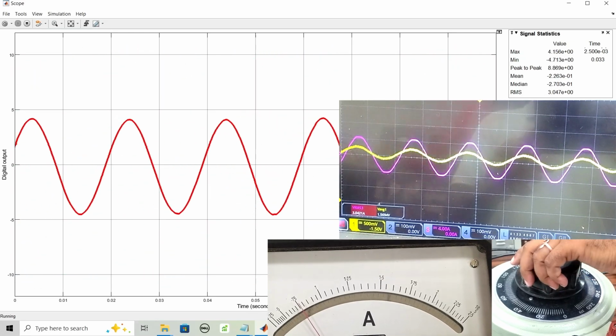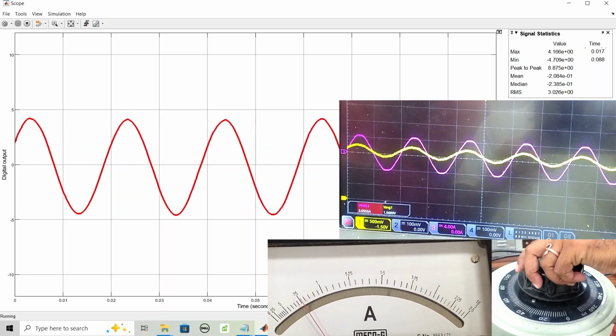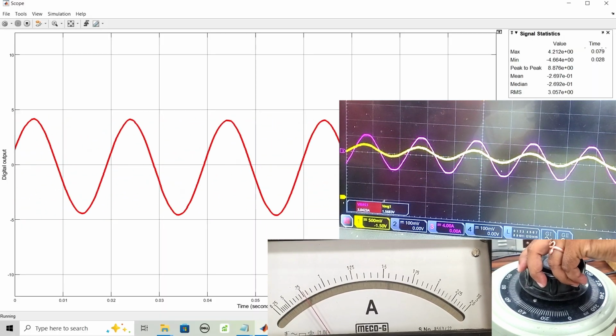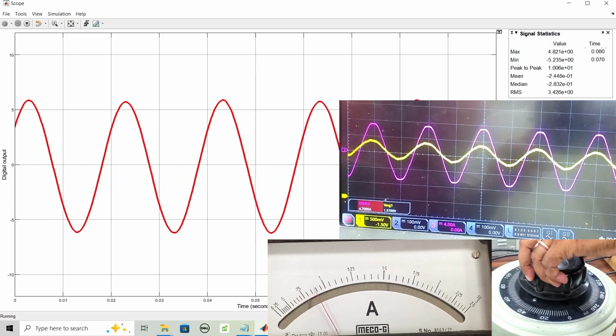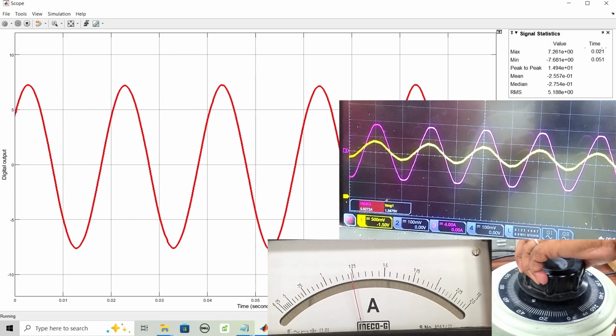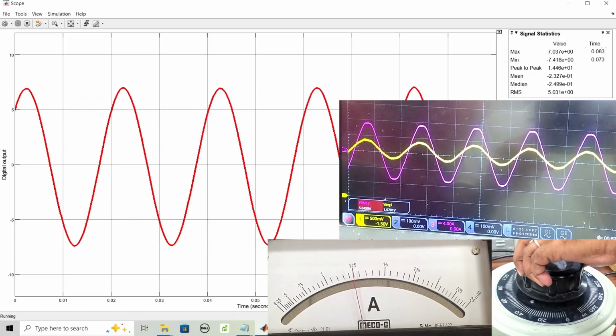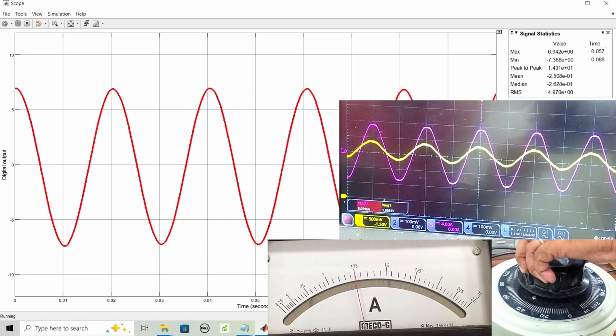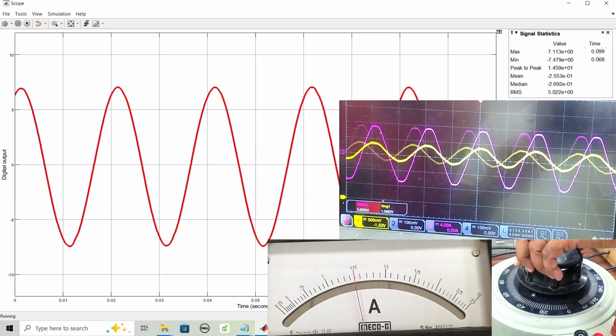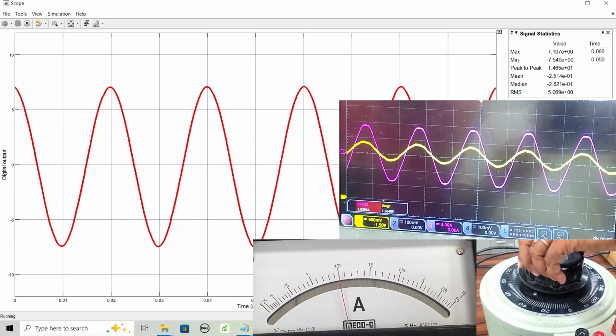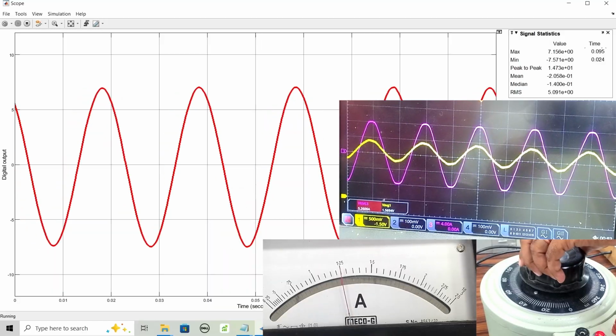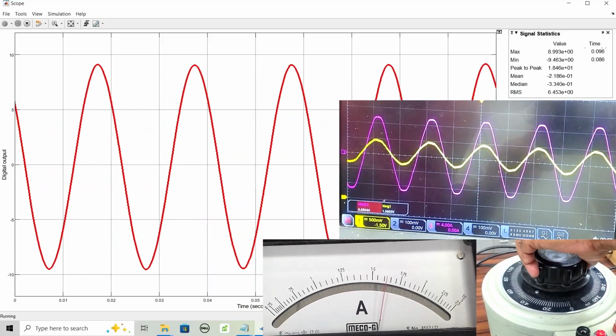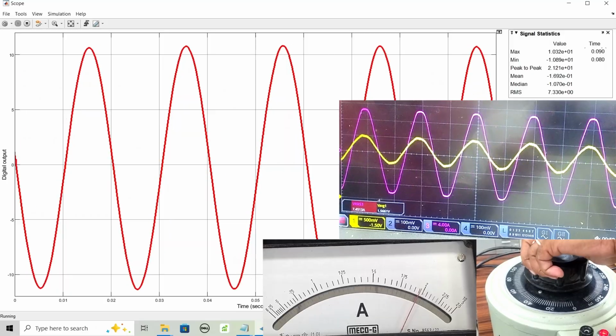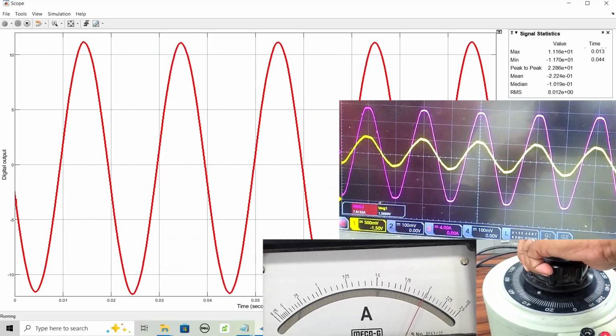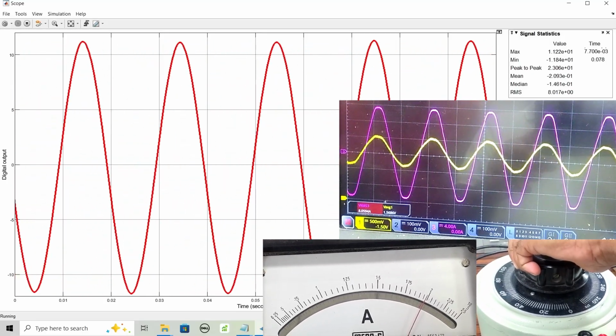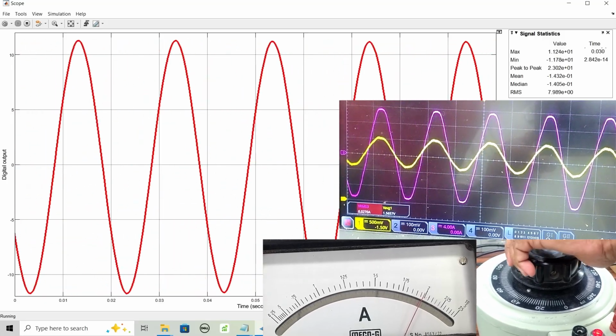Now, I will verify the sensor output at different load currents. First, I will test around 5 amperes. Here, we can observe the current value on the ammeter, the waveforms on the DSO, and the reconstructed current in the Simulink scope. Then, I will increase the load current to around 8 amperes. Again, we can compare all 3 readings on the screen. If the ammeter reading, DSO current probe value, and Simulink RMS value are nearly matching, then the sensor calibration is correct.